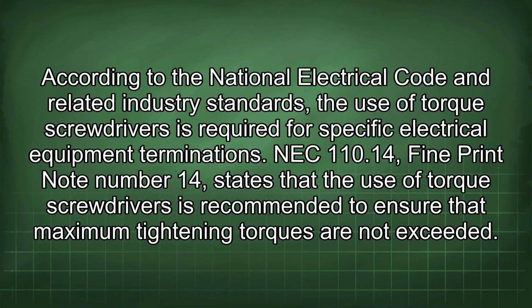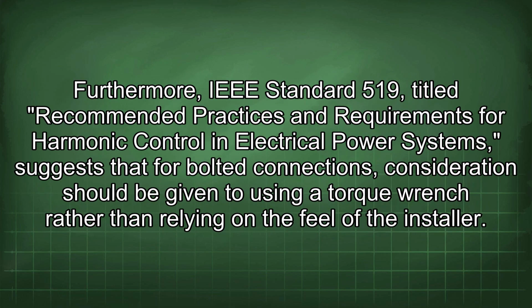According to the National Electrical Code and related industry standards, the use of torque screwdrivers is required for specific electrical equipment terminations. NEC 110.14 Fine Print Note Number 14 states that the use of torque screwdrivers is recommended to ensure that maximum tightening torques are not exceeded. Furthermore, IEEE Standard 519, titled Recommended Practices and Requirements for Harmonic Control in Electrical Power Systems, suggests that for bolted connections, consideration should be given to using a torque wrench rather than relying on the feel of the installer.